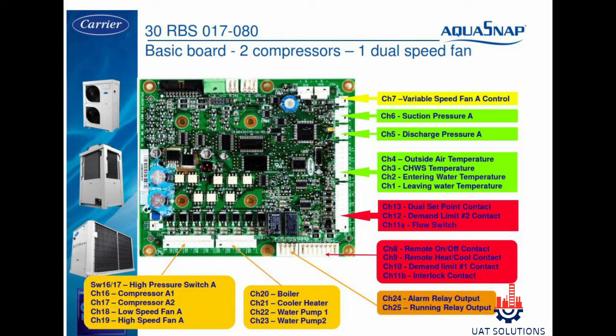High pressure switch is connected on point SW 16-17. Compressor A1 is connected on channel 16, and compressor A2 is connected on channel 17. Low speed fan circuit A is connected on channel 18, and high speed fan circuit A is connected on channel 19.